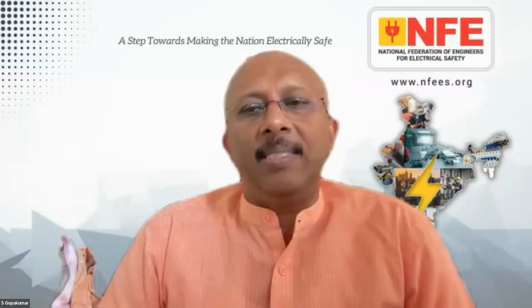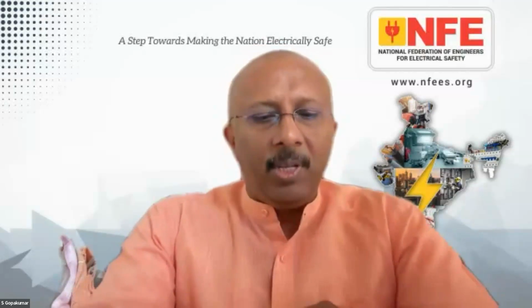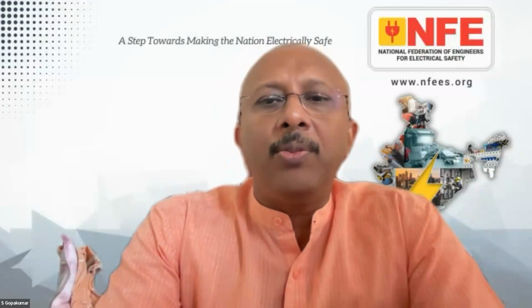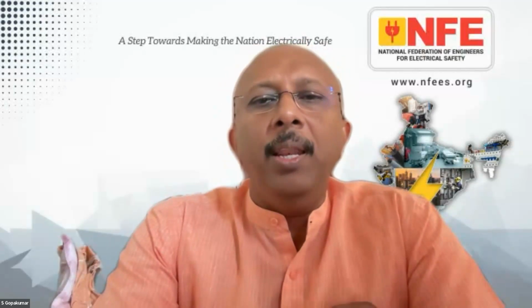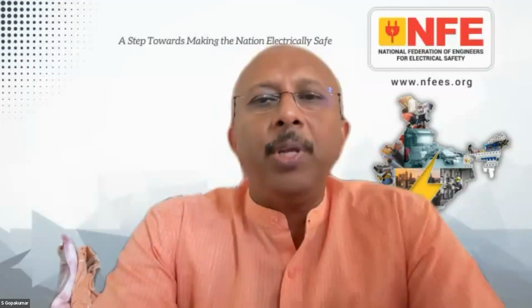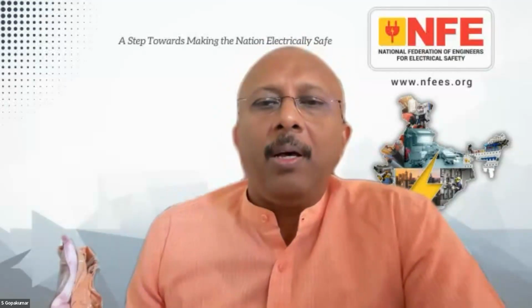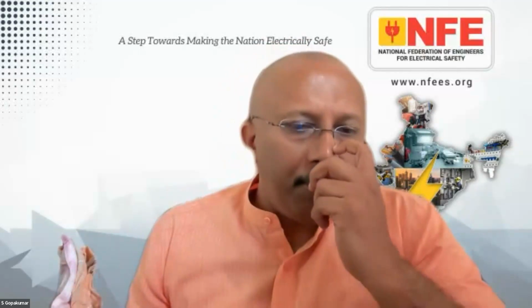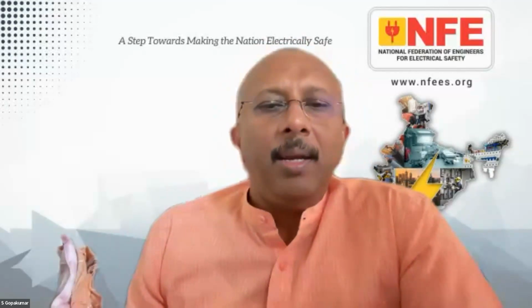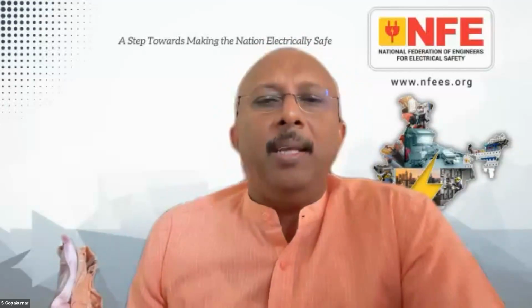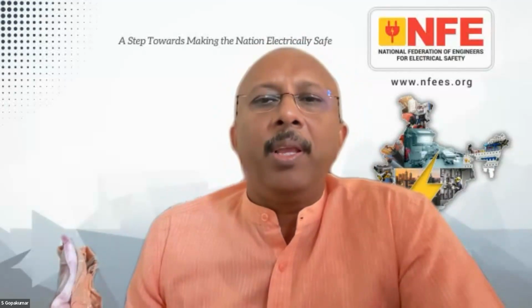But the only thing is, because this is a combination of the MCB plus RCD, we should have the type B specifically, to be used with the right characteristics, tripping values and ratings. Yes, that is very important, because the variable frequency drive or the electronics used in modern lifts produce DC leakage current. If you use a conventional AC type RCD, or the RCD part of the RCBO, the DC leakage current will blind the AC RCD. Blind in the sense it won't work during an actual AC fault.